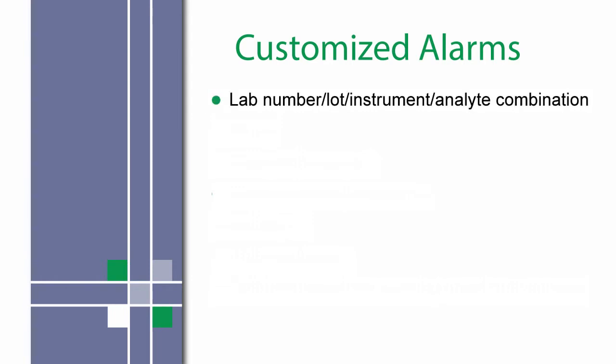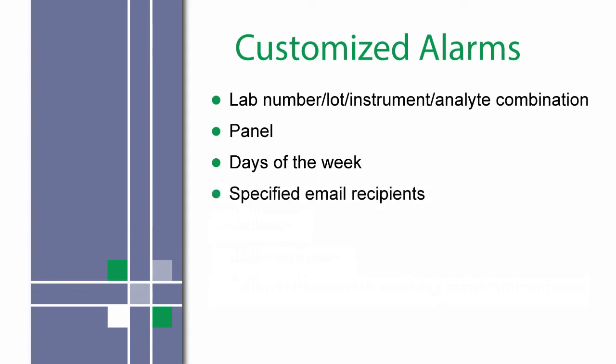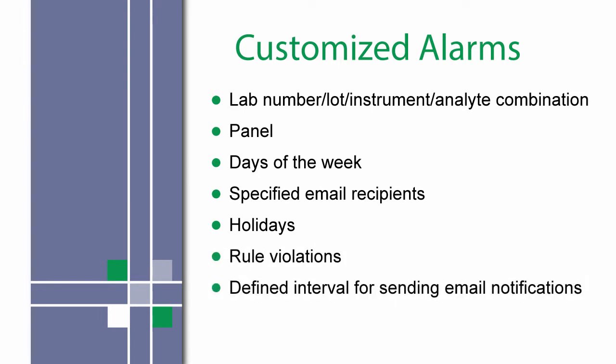Custom alarms can be set up for the following: lab number, lot, instrument, analyte combination, panel, days of the week, specified email recipients, holidays, rule violations, and a defined interval for sending email notifications.